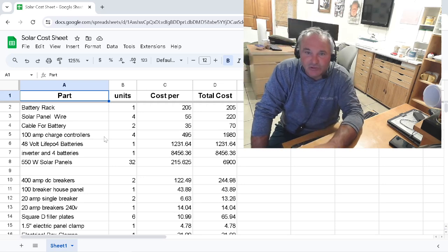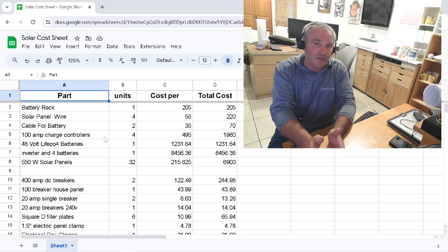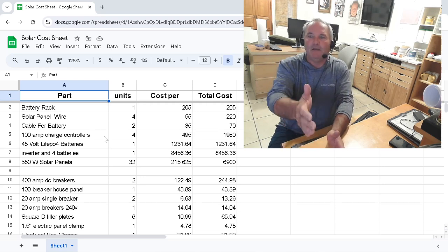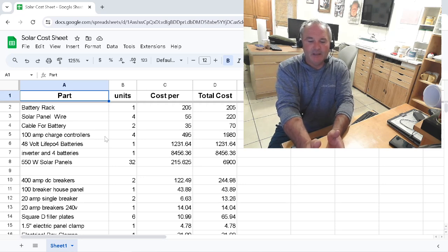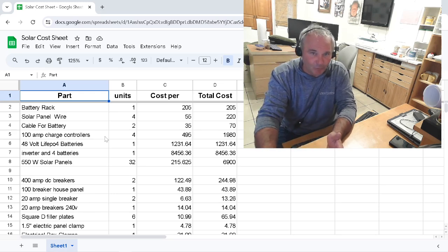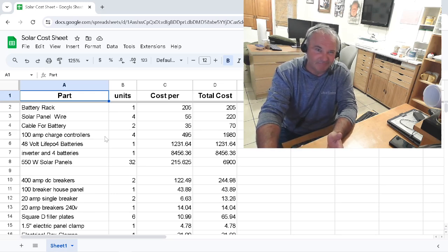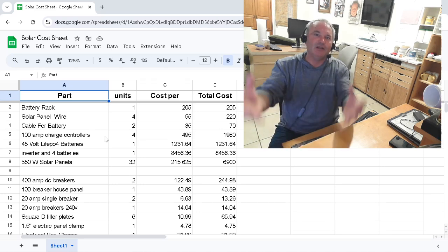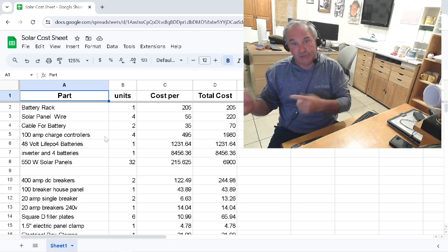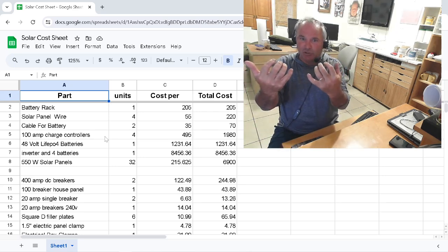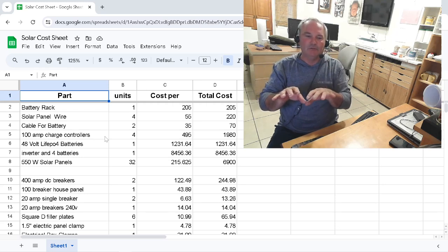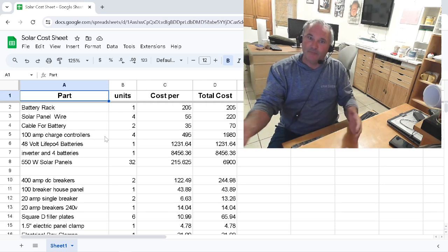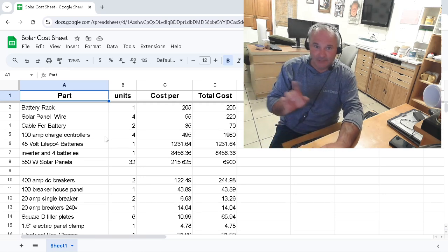So that is the charge controller. When those batteries are full, let me get back to what I was saying. At 7 o'clock I leave, those batteries are maybe 25%, 30% around there somewhere. I can check them. I know that when I'm at about 30% at 7 o'clock in the morning, they're completely full by 10:30, 11 right now, early July. By 11 o'clock, they're full. So those charge controllers are now limiting the power they will push to the batteries to charge the batteries. The batteries are full. So the charge controllers say, nope, don't give them more power. Just give them what the house is using. So if you overload them with the PV wattage coming in from the solar panels, they will get hot. And that's not good.